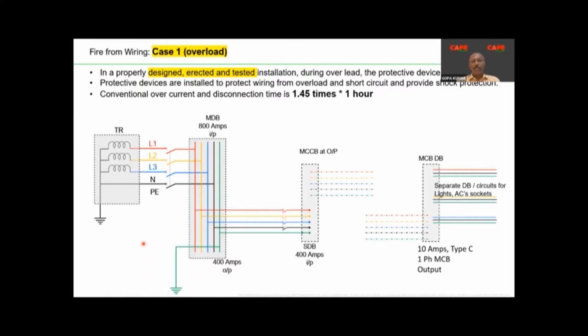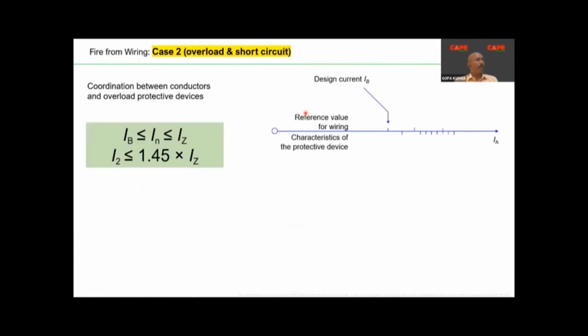If somebody says that fire is created because of overload, that means it is not because of overload. It is because your devices didn't trip. Starting from the transformer, we have circuit breakers, MCCBs, MCBs, and so many protective devices. Why these devices are not protecting your equipment is the first question to be asked. Of course, with a properly designed, erected and tested installation, the chance of fire with respect to overload is very much less. And you see here 1.45 times, 1 hour, the protective device, the conventional disconnection time. A lot of scientific things come into this particular case.